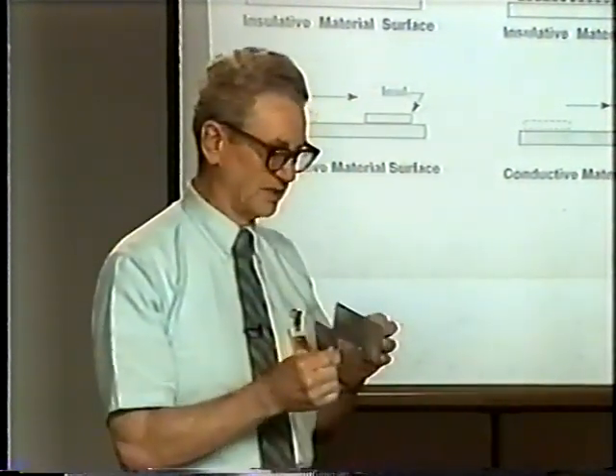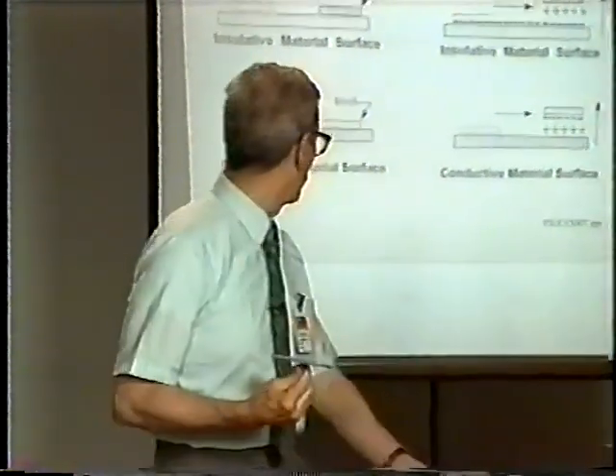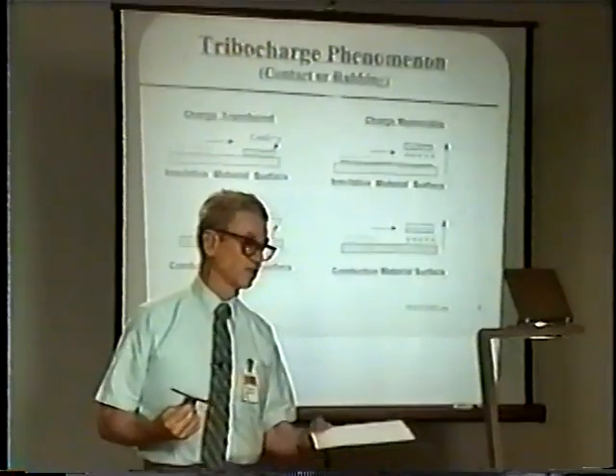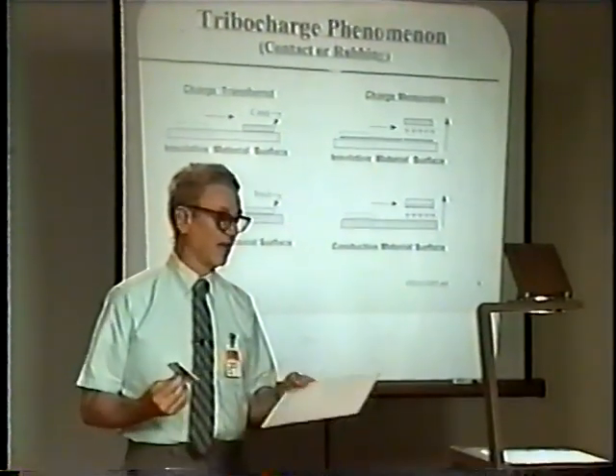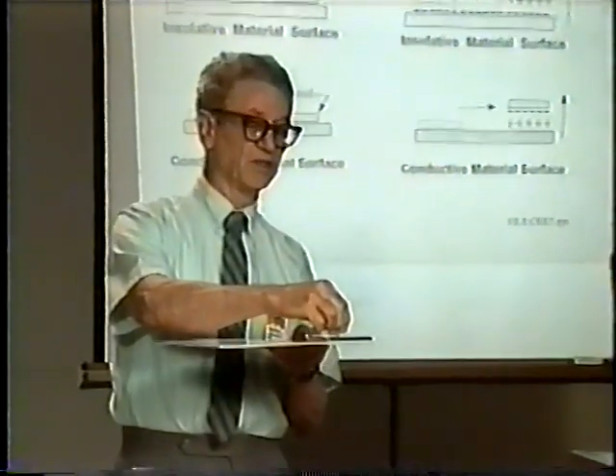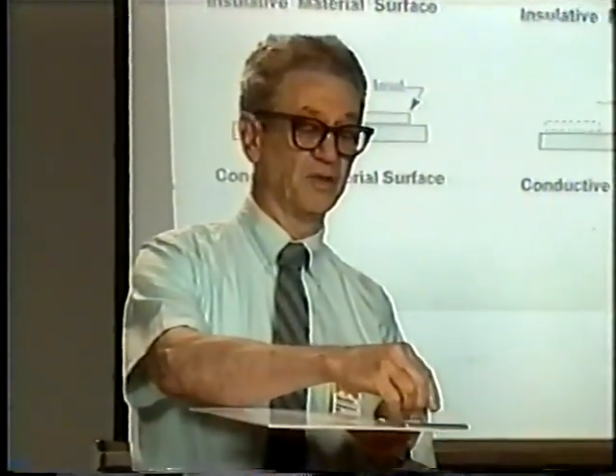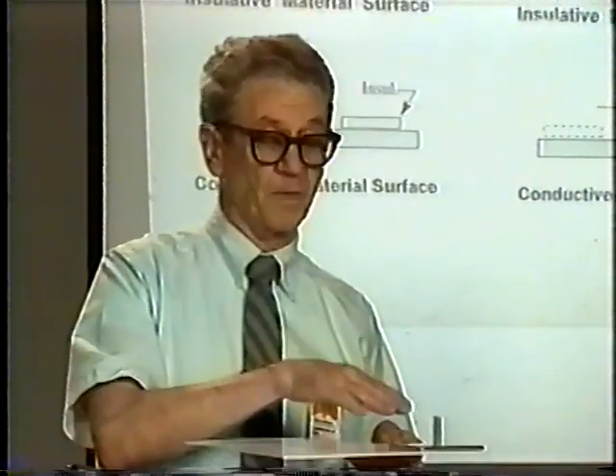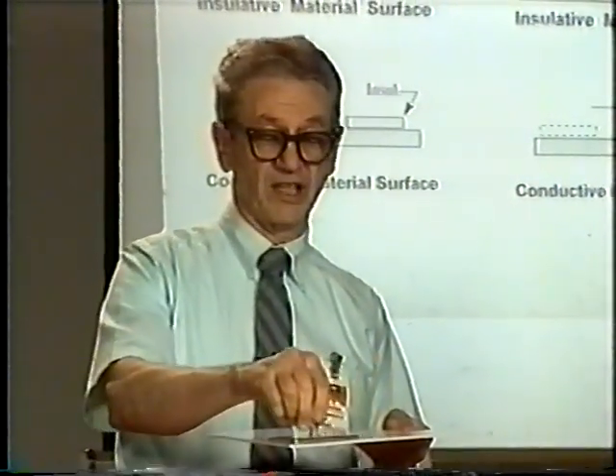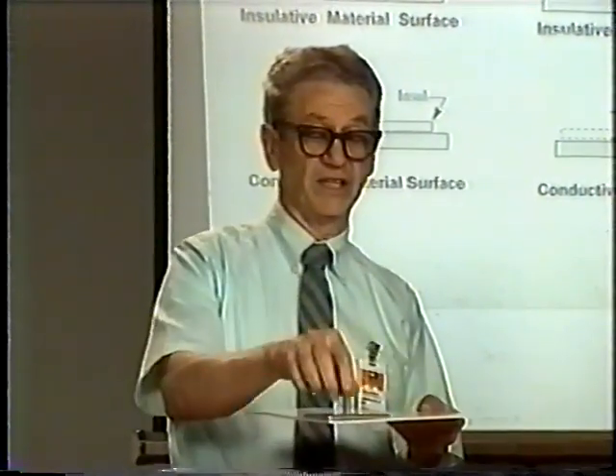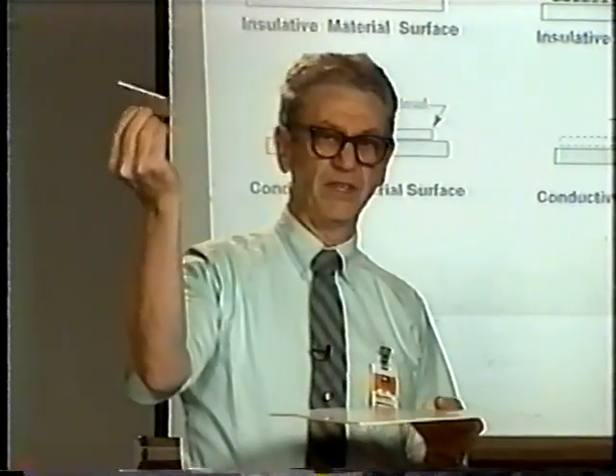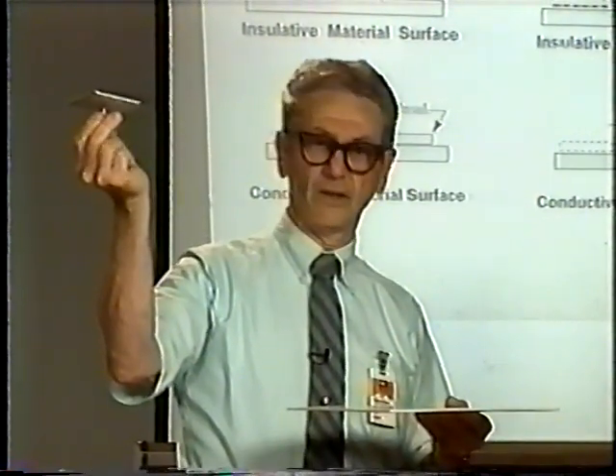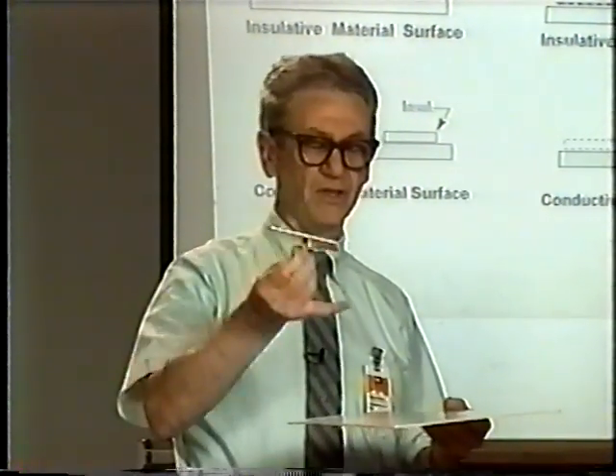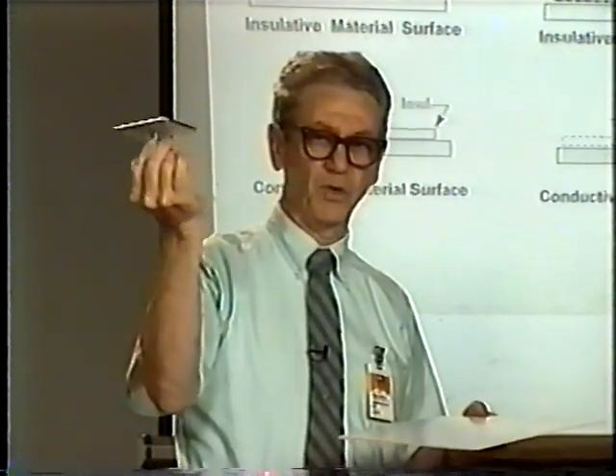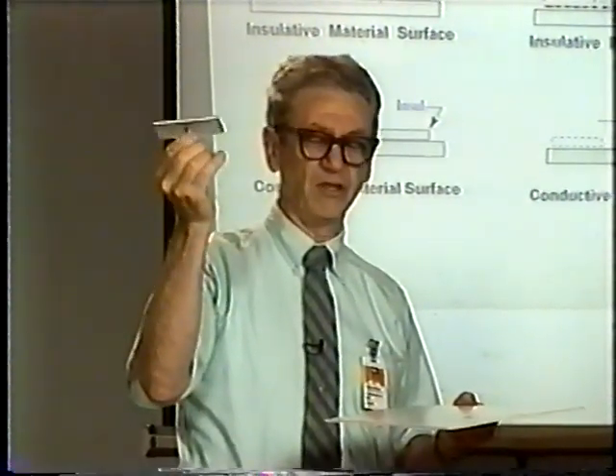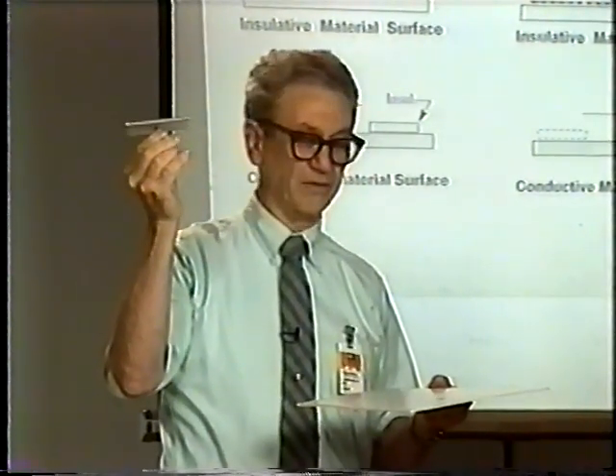In the tribocharging instance where we talked before about the surface being insulative, I have a piece of Teflon here. To illustrate that example, when I put this metal plate down on the Teflon, it has picked up charge. If I slide this along, as I explained earlier, the charge will stay on the insulator. Now when I lift it up, this plate has a capacitance, and there's a field line going back to the Teflon, back to me, back to the world. It's this field that is a potential source of damage to electronic devices.